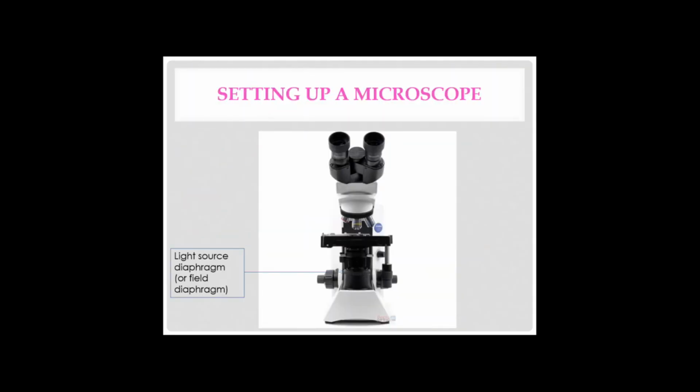To adjust the microscope, there are several settings to use for cytology and hematology. The diaphragm and the light source on the field of view must be open to allow as much light to pass through as possible. Secondly, the condenser should be as close as possible to the slide. Here you can see the dial, which allows you to move the condenser up and down.